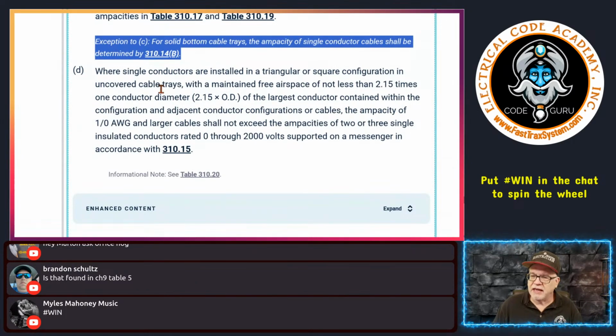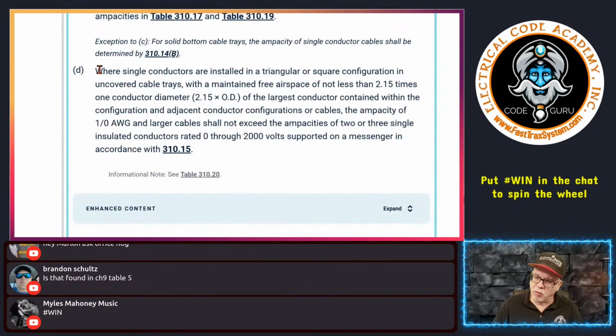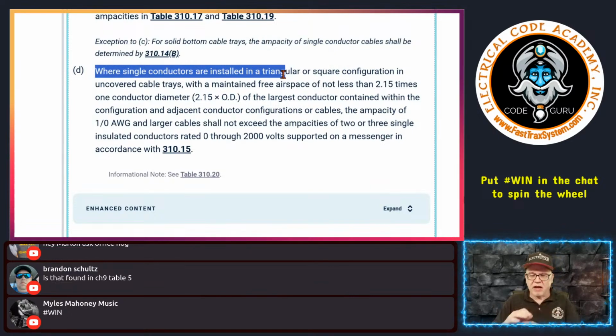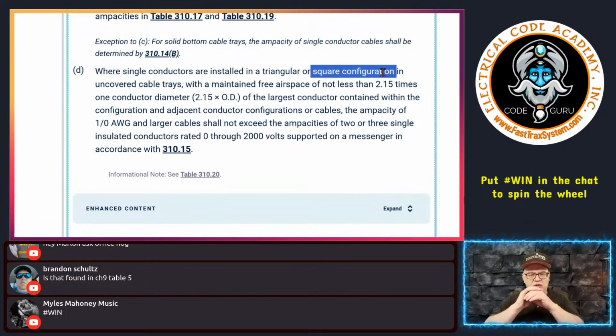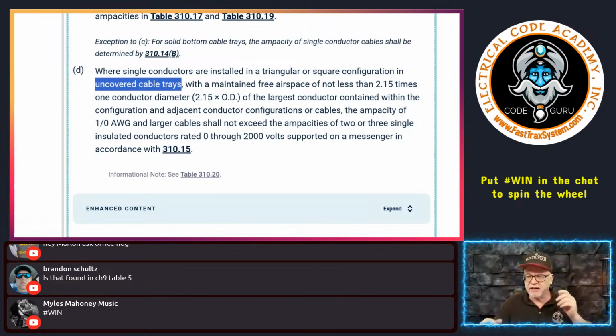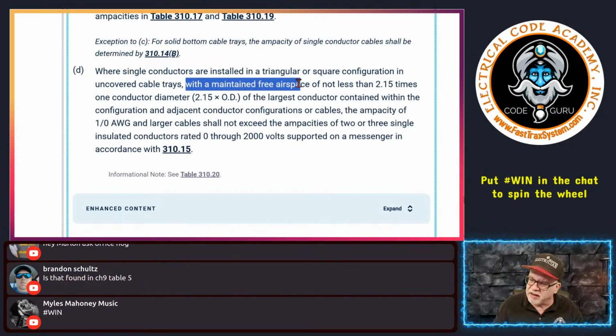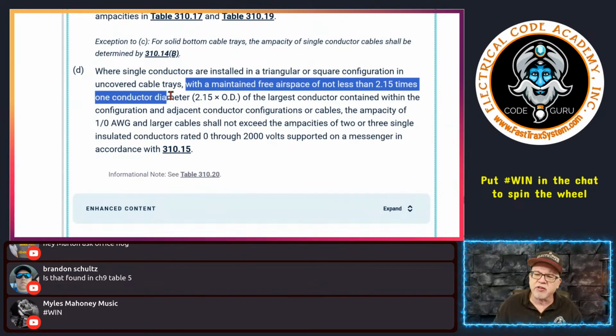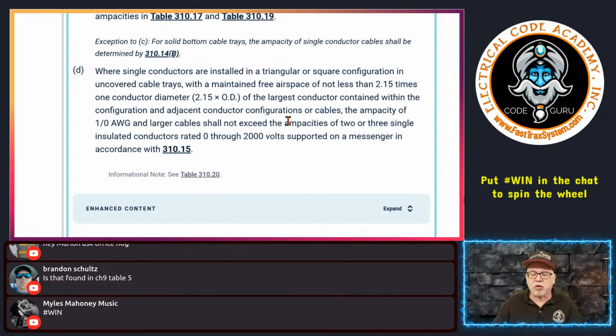All right, now lastly, D. D says, now where single conductors are installed in a triangular triad, I'll show you a picture of that, or a square configuration, 4 conductors, basically a square or diamond configuration, in an uncovered tray, so there's no cover on it, so we're allowing heat to ventilate, okay? It says, with a maintained air spacing of not less than 2.15 times one conductor's diameter, and it's going to be the largest conductor's diameter amongst the configuration, whether it's a triad of 3 or the 4-conductor diamond square shape. You take the largest conductor in the configuration, and it's going to be 2.15 multiplied by the OD of the largest conductor in that configuration. And that's the spacing between the next configuration of triads or quads or whatnot.